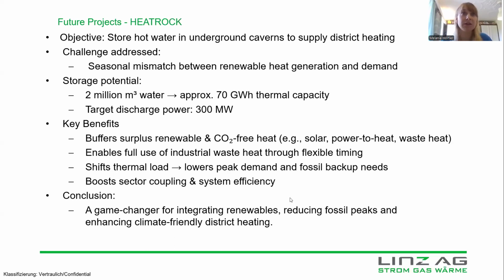The key benefits of a large-scale thermal storage: it absorbs surplus renewable heat during high production periods and releases it when demand is high. This prevents curtailment and enables peak shaving. It also allows flexible use of industrial waste heat, which often doesn't match demand times. Stored waste heat can be fed into the district heating system when needed, reducing reliance on fossil peak boilers. By shifting heat feed-in over time, storage improves network efficiency, lowers fuel use and CO2 emissions, and stabilizes the system.